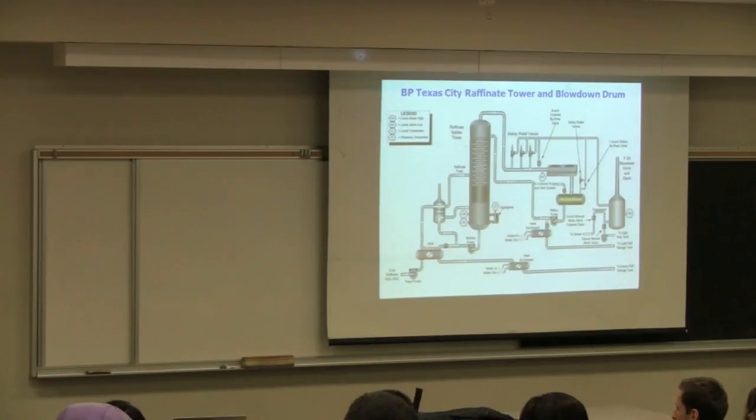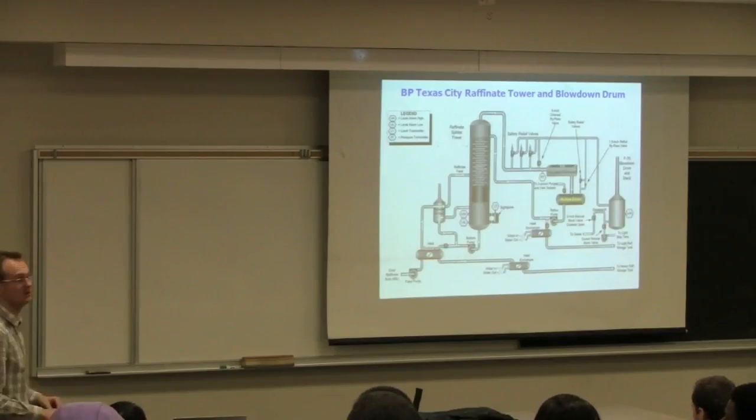So just to update half of you, there was a part of the video that showed how a lot of the sensors had maintenance work orders open for them. But those orders were closed as being completed without the work being done. So that was one of the major discoveries: for example, maintenance on some of those level sensors and alarms was noted as being completed but hadn't actually been executed. So those sensors were not in a working state, but could have been.